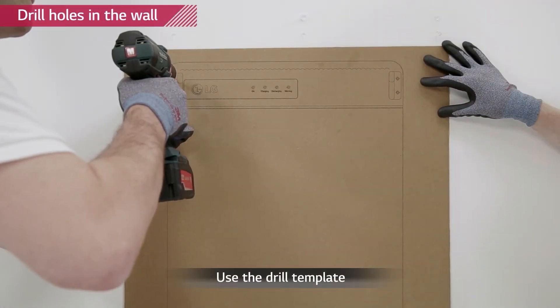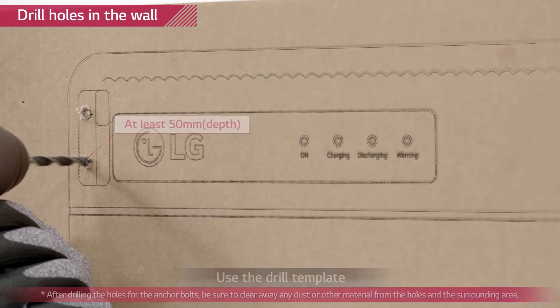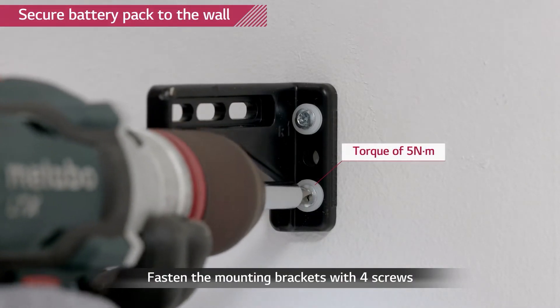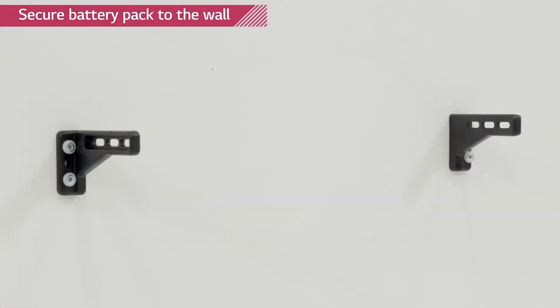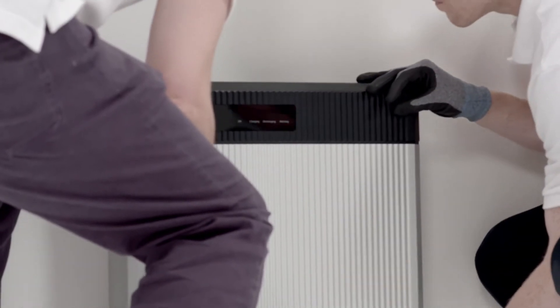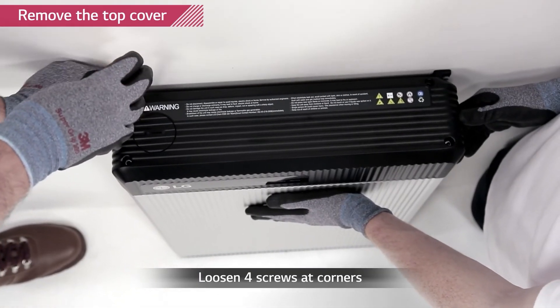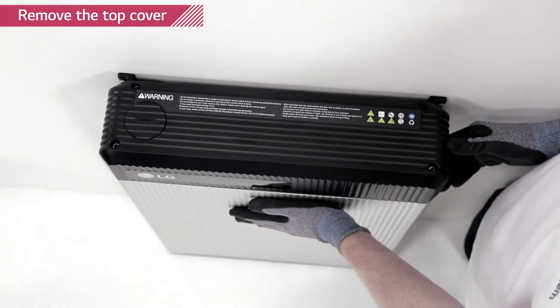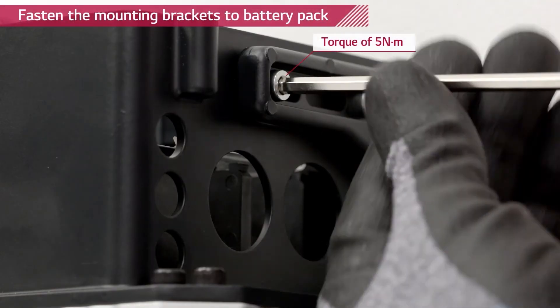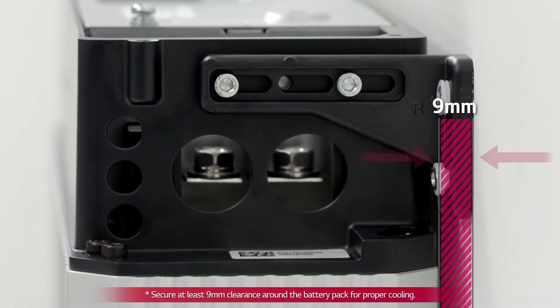Drill four holes into the wall for M6 screw anchors using the drill template. The depth of each hole should be at least 50 millimeters. Fix the provided mounting brackets to the wall with M6 screw anchors with a torque of 5 newton meters. Place the RESU battery pack between the wall mounting brackets. Loosen the four screws on the top cover and remove it. Fix the RESU battery pack to the mounting brackets using M5 hex socket screws with a torque of 5 newton meters. Remember that the battery pack needs to have a distance of at least 9 millimeters away from the wall.